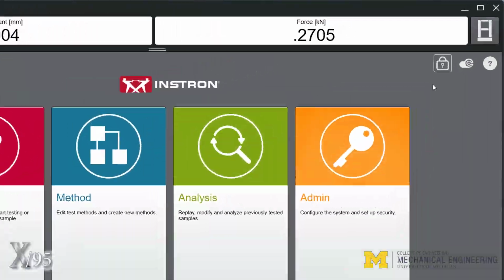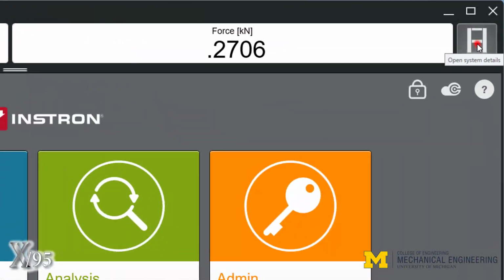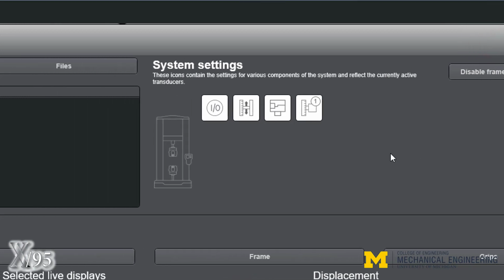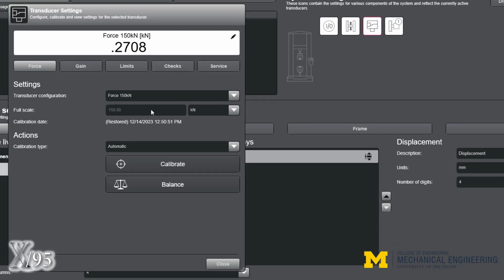Click the frame icon located in the upper right. Select the load icon from the transducer status bar. In the pop-up window, verify the 150 kilonewton load cell is the selected transducer, then click on the Calibrate button.